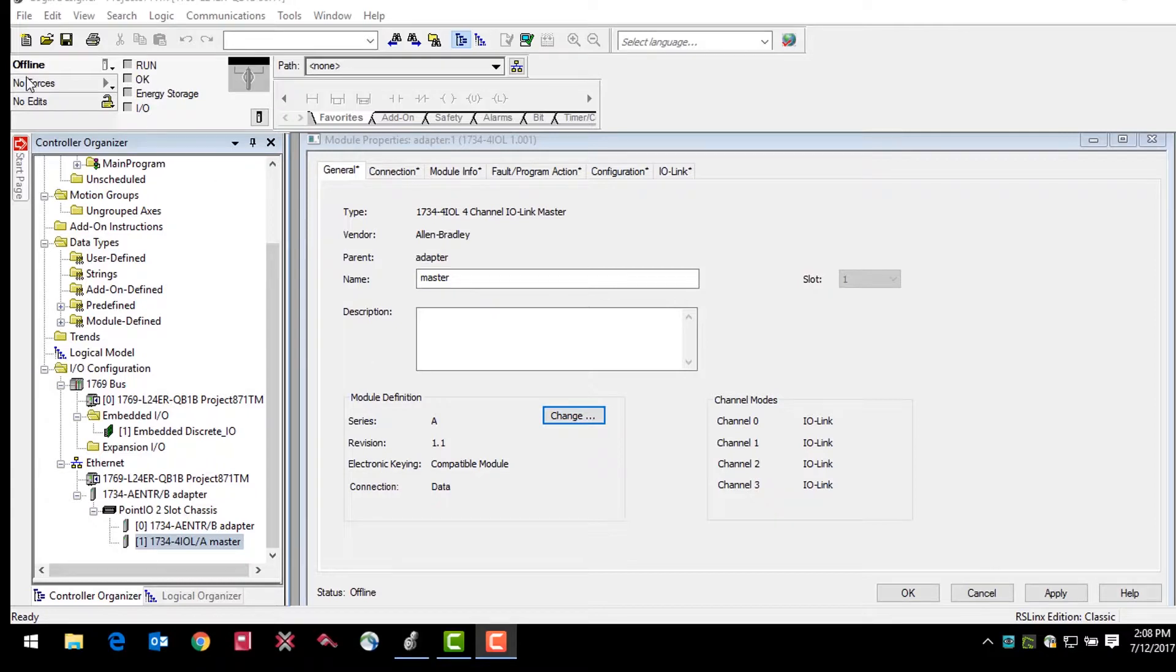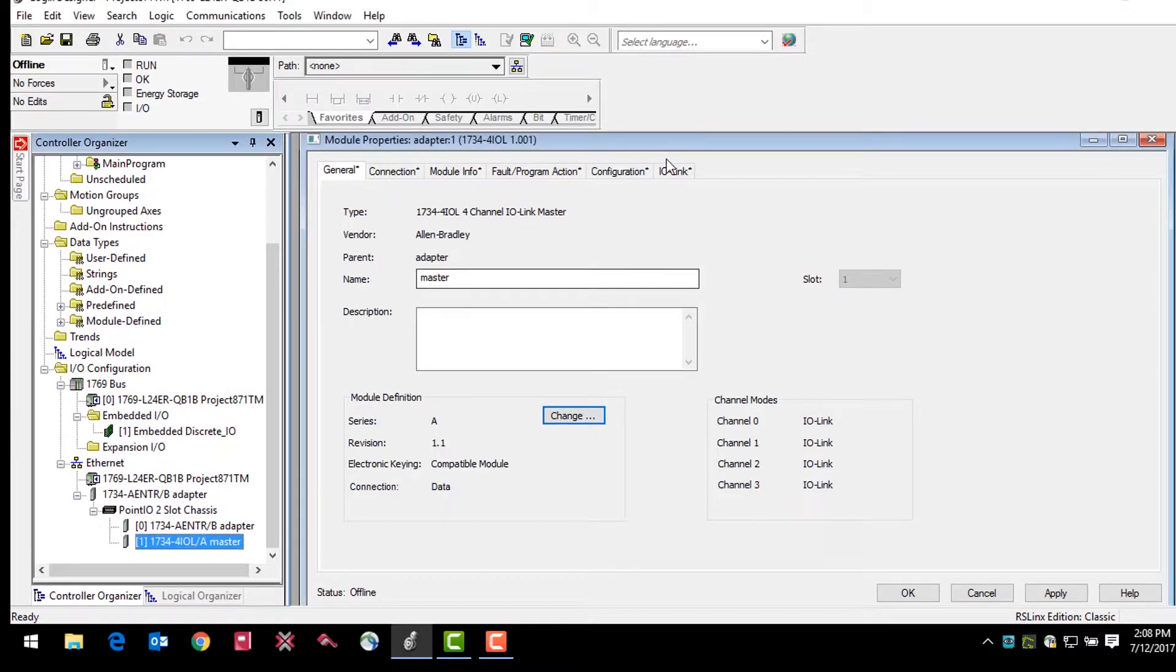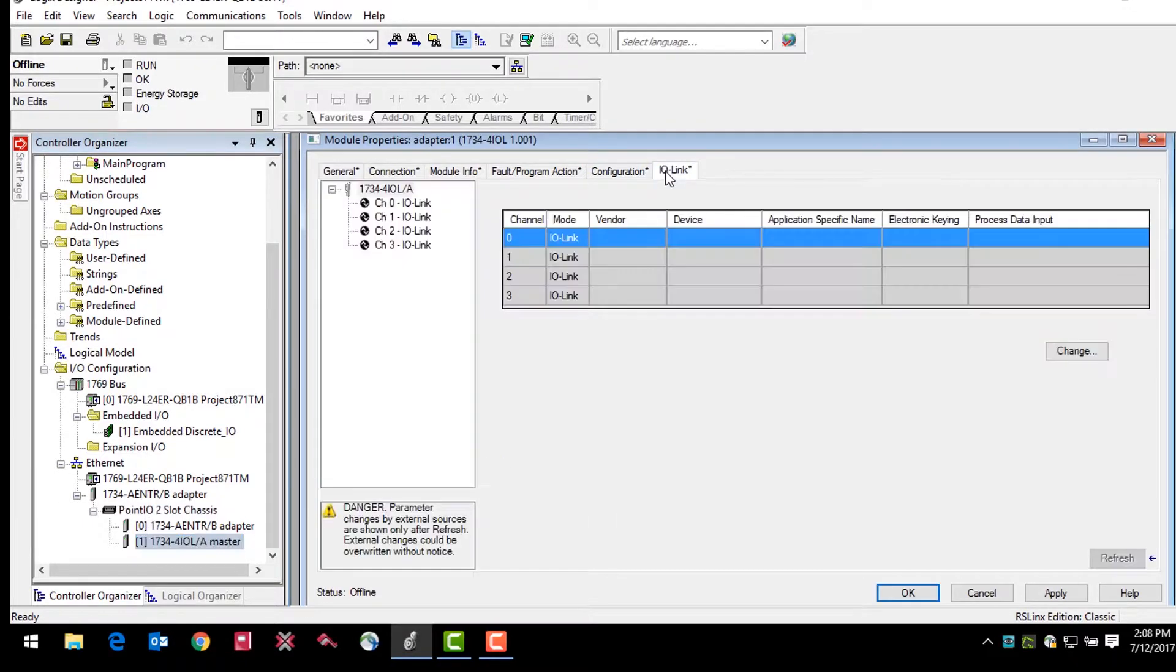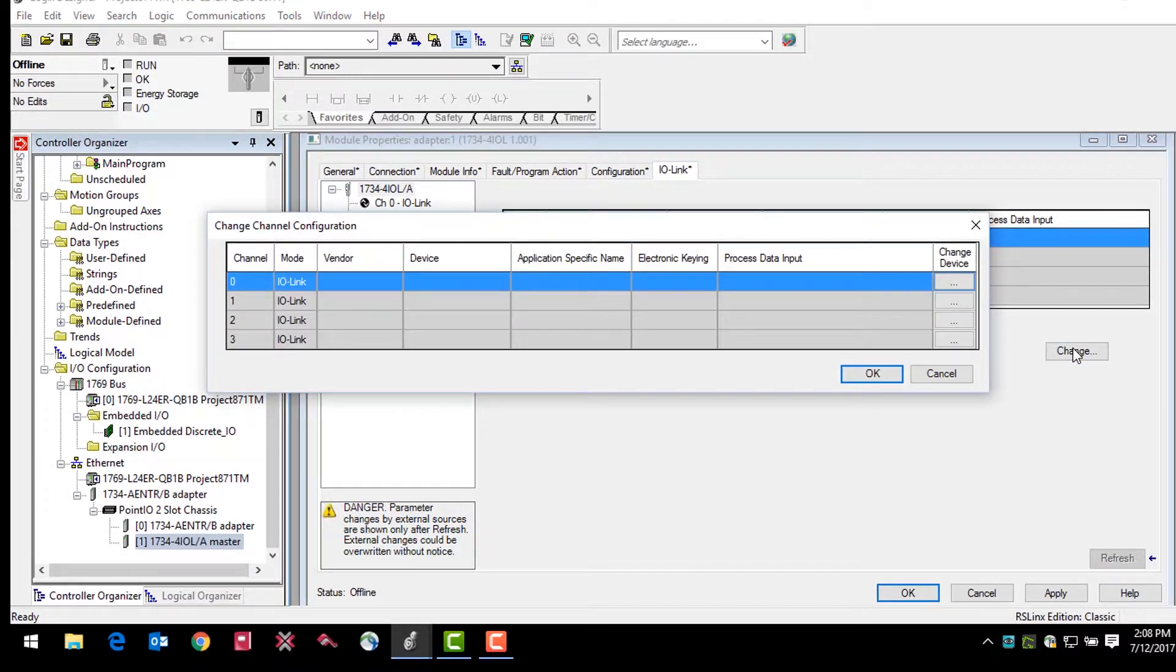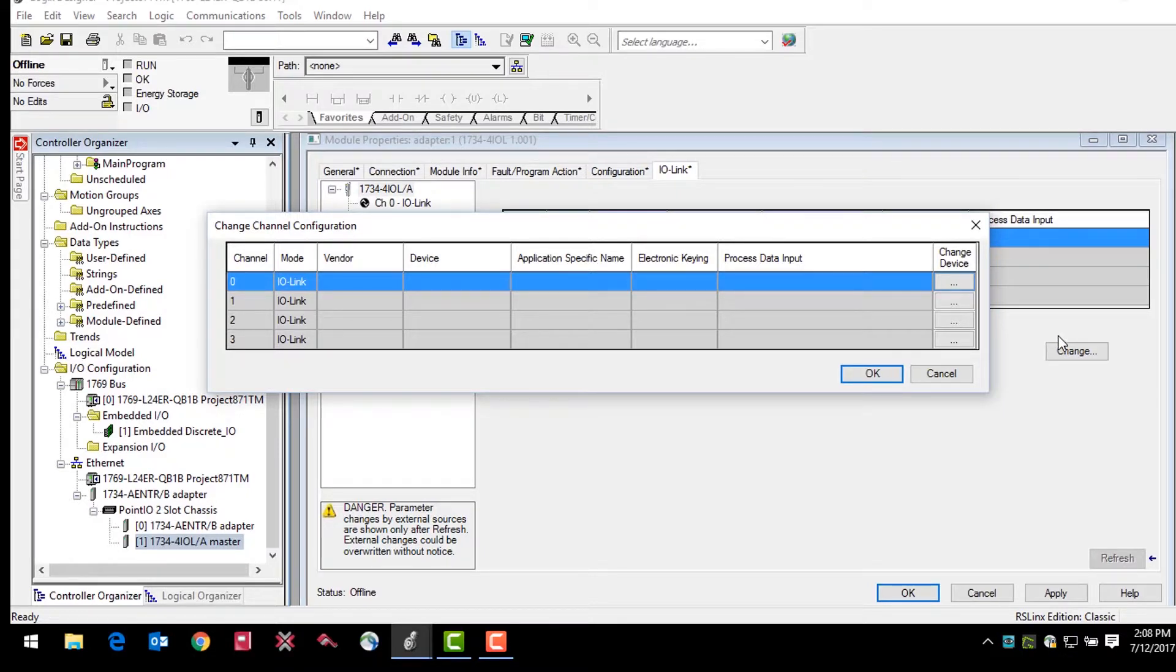First, you'll want to take the controller offline and add a device to the IO-Link master. Click on the master module in the device tree and then select the IO-Link tab in the module properties window. From here, select the button that says change, highlight the channel where you would like to add a sensor on the master, in this case channel 0, and click the change device button.